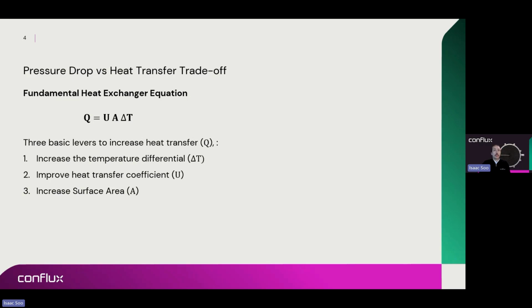We do have some control over the U, the heat transfer coefficient, where we can promote turbulence and disrupt the flow within our heat exchanger itself. But you often find yourself limited or bound up by the fluid properties themselves. So no matter how much you increase the interaction with the wall, the inherent conductivity, etc., of the fluids can still limit the U value. So we get the most bang for our buck by being able to pull the lever of surface area. And that way we're able to cram as much geometry as possible into a small volume and maximize heat exchange to volume ratio.